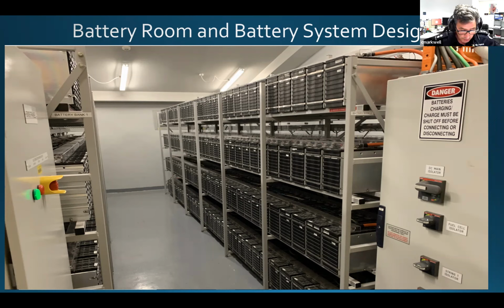And so in total, there were some 1,064 batteries in the system, all of them rated at 3 volts DC with a capacity of 400 amp hours each. So each battery bank, as a holistic bank, was controlled by an individual switchboard isolator, and you see that on the right. And each string had its own isolation management system. So they're numerically identified, and this was important in the review of the battery management system data, numerically identified from the top to the bottom as 1, 2, 3, and 4 being the lowermost string.